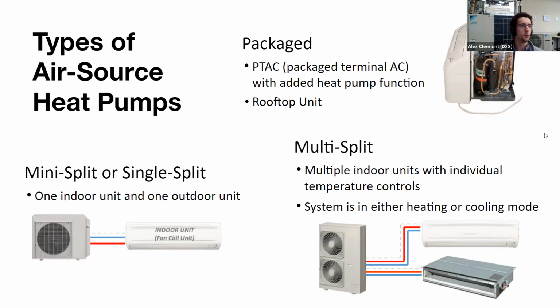So now we're starting on the different types of air source heat pumps. What we're looking at here at the top is a PTAC, or package terminal AC, and these are often seen in hotels or apartments. It takes heat from the room and throws it outside. Some of them also come with the heat pump function, again, the key component being that reversing valve, as we previously discussed. Then it will take heat from outdoors and bring it inside. Now, these don't work down to very low temperatures, so oftentimes you'll see these with electric heat in there as well.